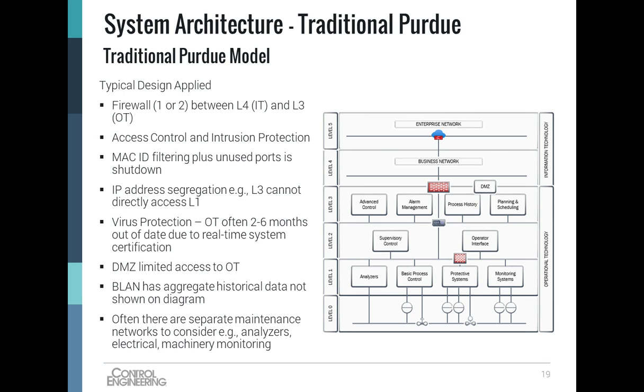There's typically a DMZ with limited access to OT. Often the historian is a common path for routing through the DMZ. The business LAN has aggregate historical data not shown on the diagram - at the business network or enterprise level, where historical data is hosted for use. Often there are separate maintenance networks to consider, for example an analyzer maintenance network, an electrical network, a machinery monitoring network perhaps. There are other options there as well that plants do have.